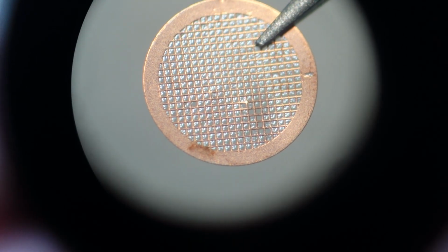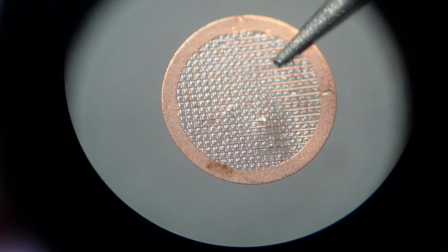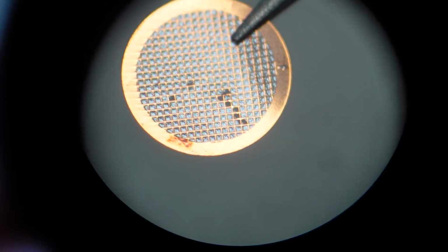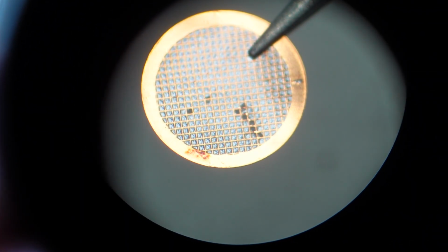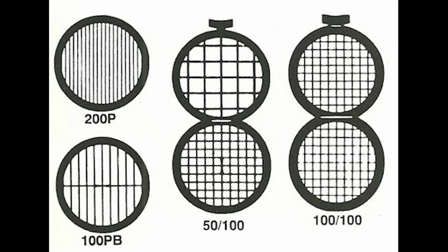Samples are usually placed on 3 mm wide grids made from materials like copper or gold. These grids have a carbon support film that holds your sample in place. If you want to tilt the sample, for example in tomography, a grid with fewer mesh lines is better.